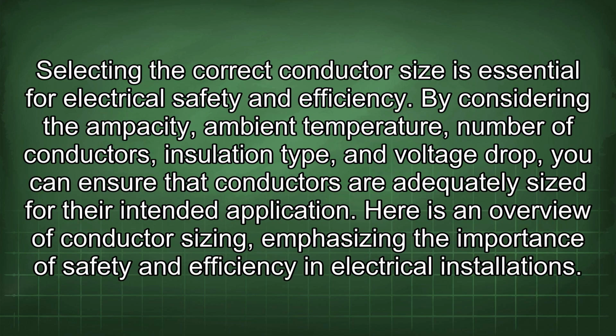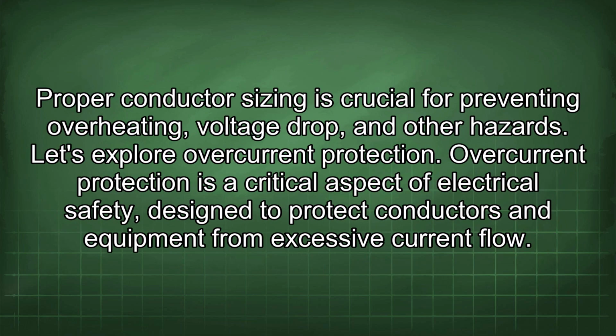Selecting the correct conductor size is essential for electrical safety and efficiency. By considering the ampacity, ambient temperature, number of conductors, insulation type, and voltage drop, you can ensure that conductors are adequately sized for their intended application. Here is an overview of conductor sizing, emphasizing the importance of safety and efficiency in electrical installations. Proper conductor sizing is crucial for preventing overheating, voltage drop, and other hazards.